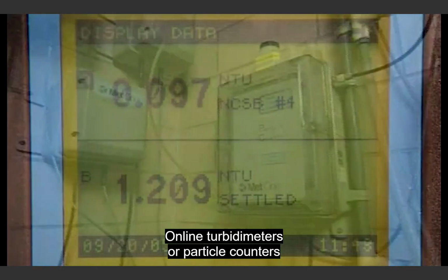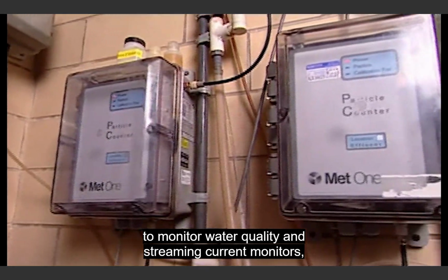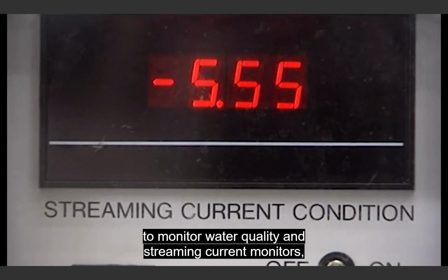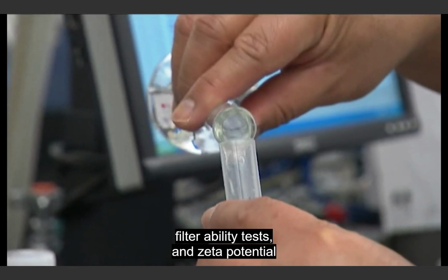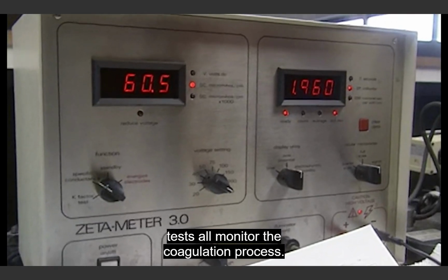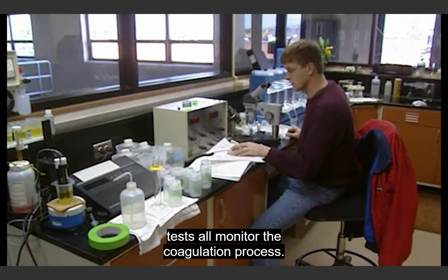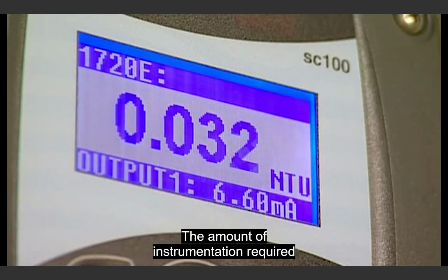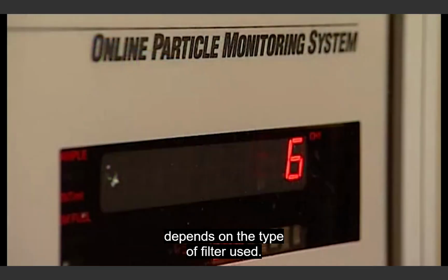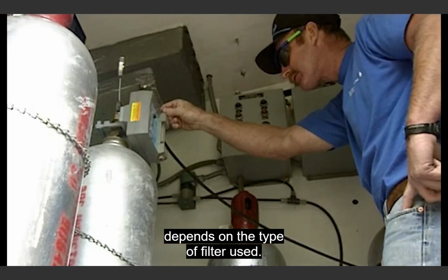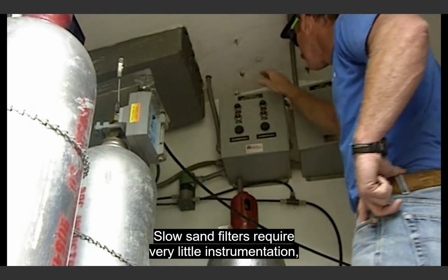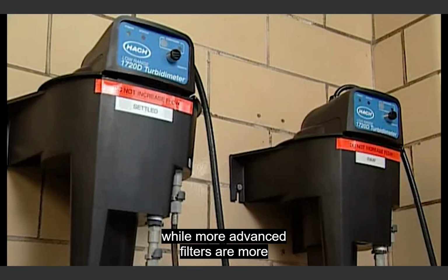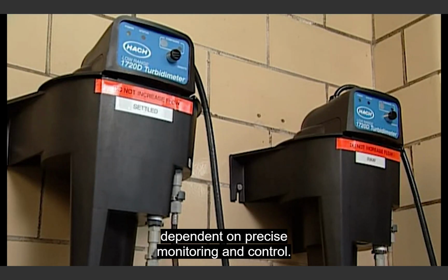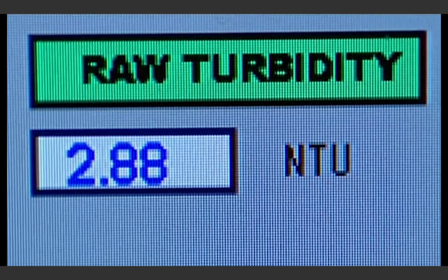Online turbidimeters or particle counters monitor water quality, and streaming current monitors, filterability tests, and zeta potential tests all monitor the coagulation process. The amount of instrumentation required depends on the type of filter used. Slow sand filters require very little instrumentation, while more advanced filters are more dependent on precise monitoring and control.